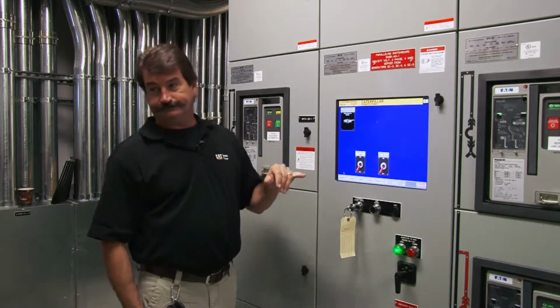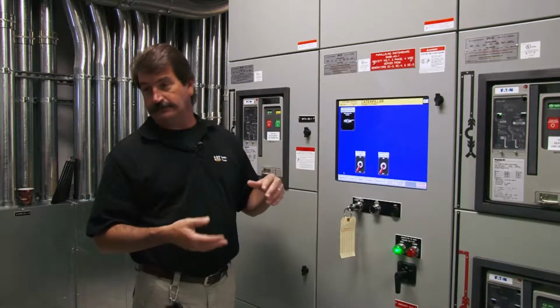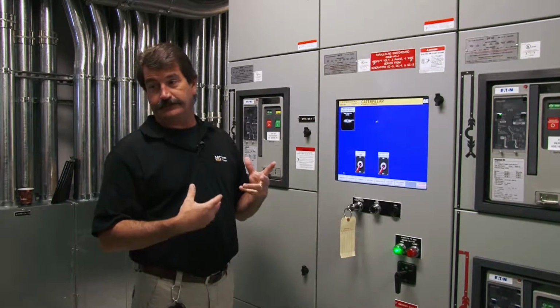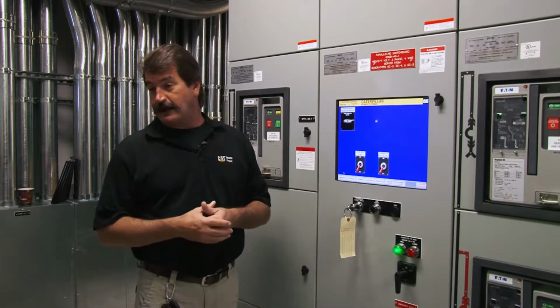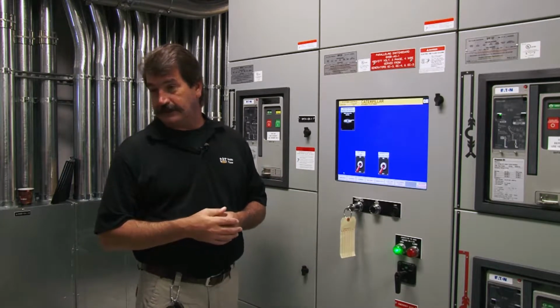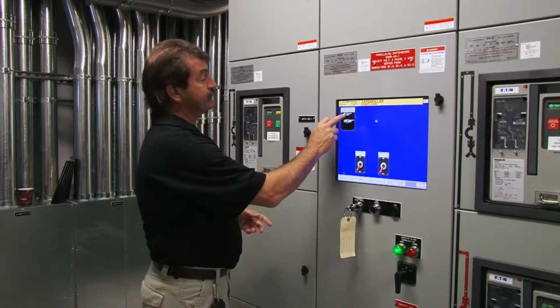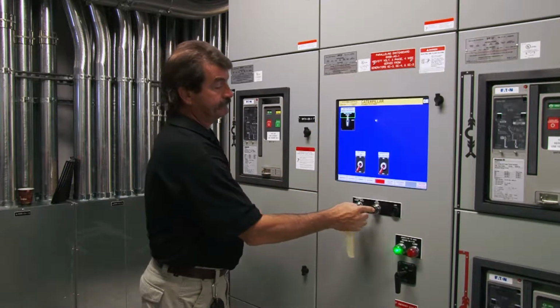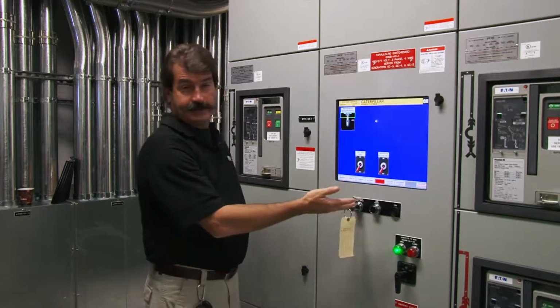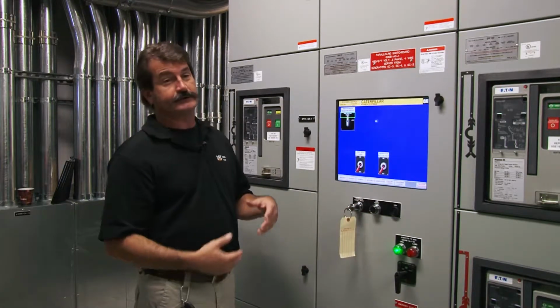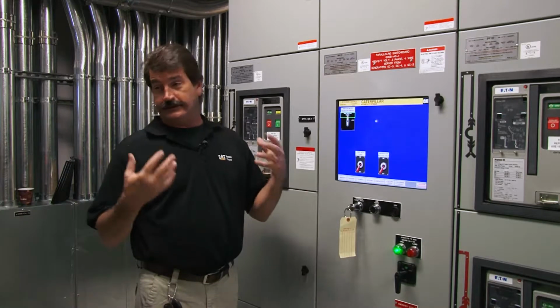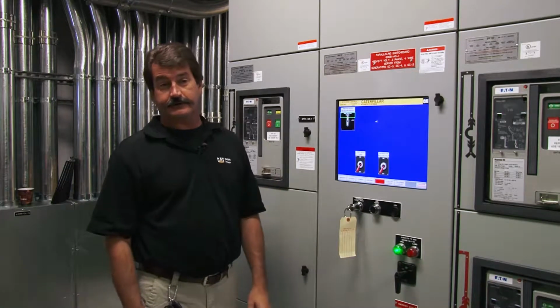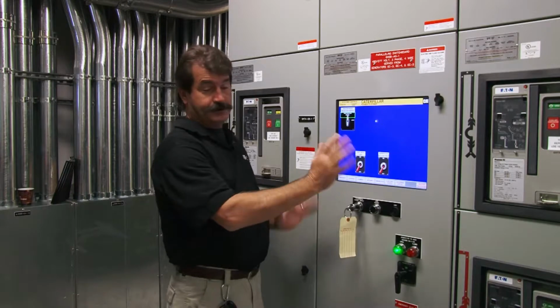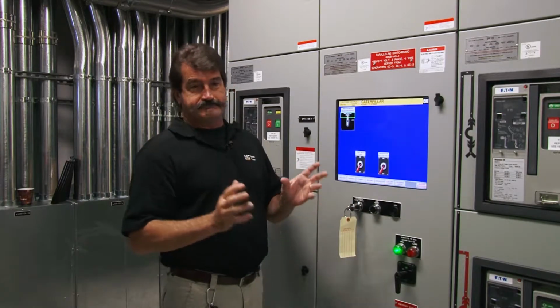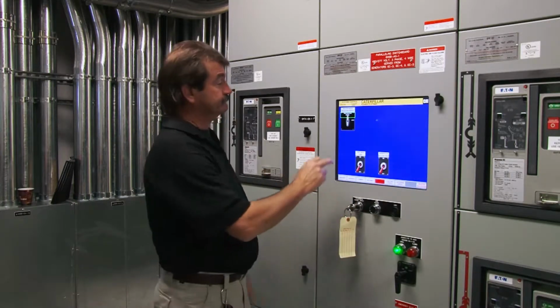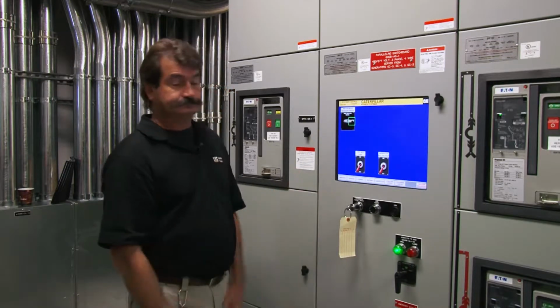Going to manual, it's not going to ask you about going to manual. If you do go to manual, you're not going to get the automatic operation you want. If you go to manual there, that will let you know you've got a problem, because when you're in manual and you lose power, your gens are not going to start up. Your breakers are not going to close. No automatic action is going to happen. So we'll go back to auto, and we're happy that way.